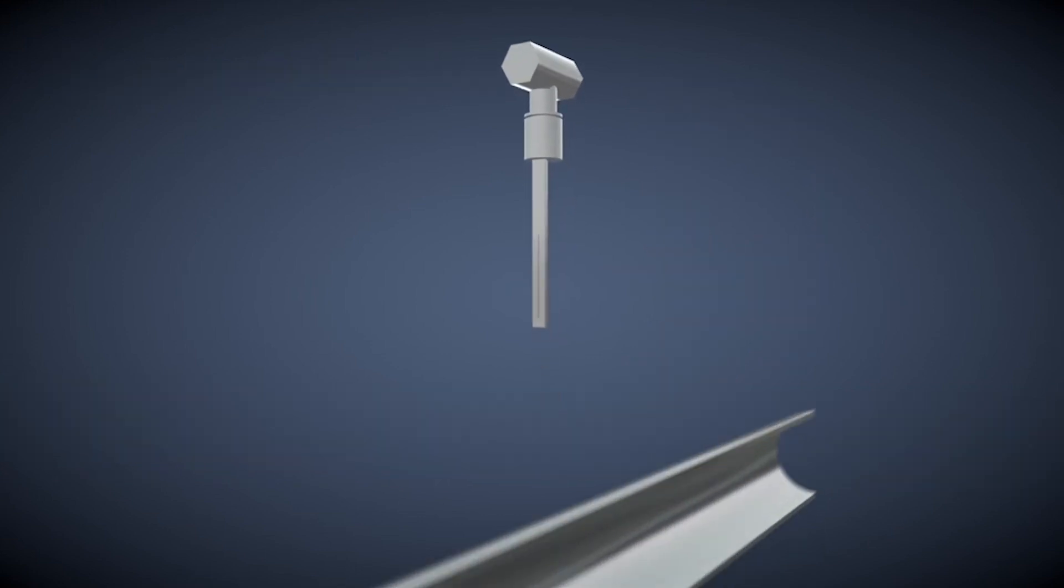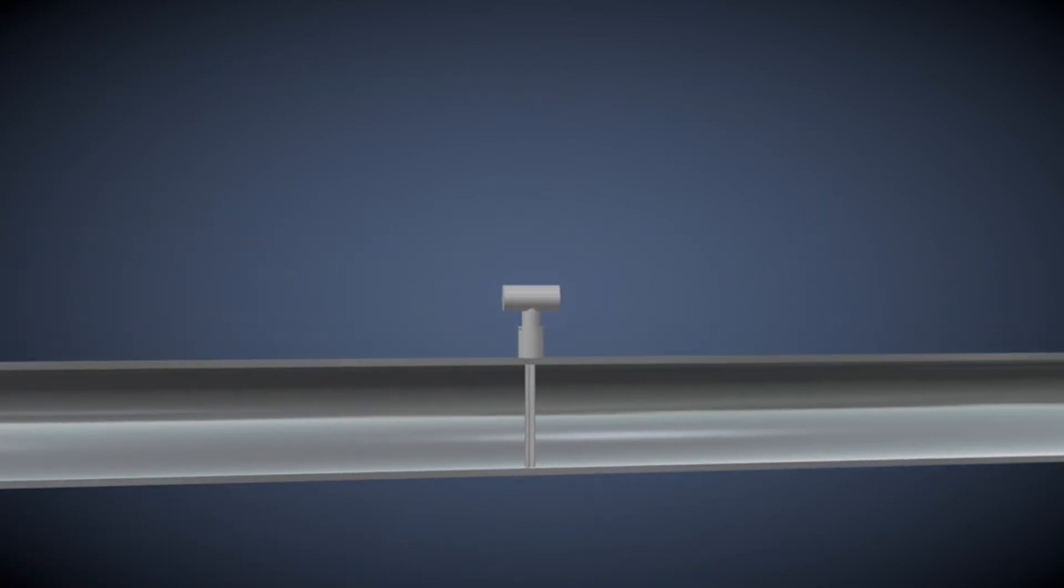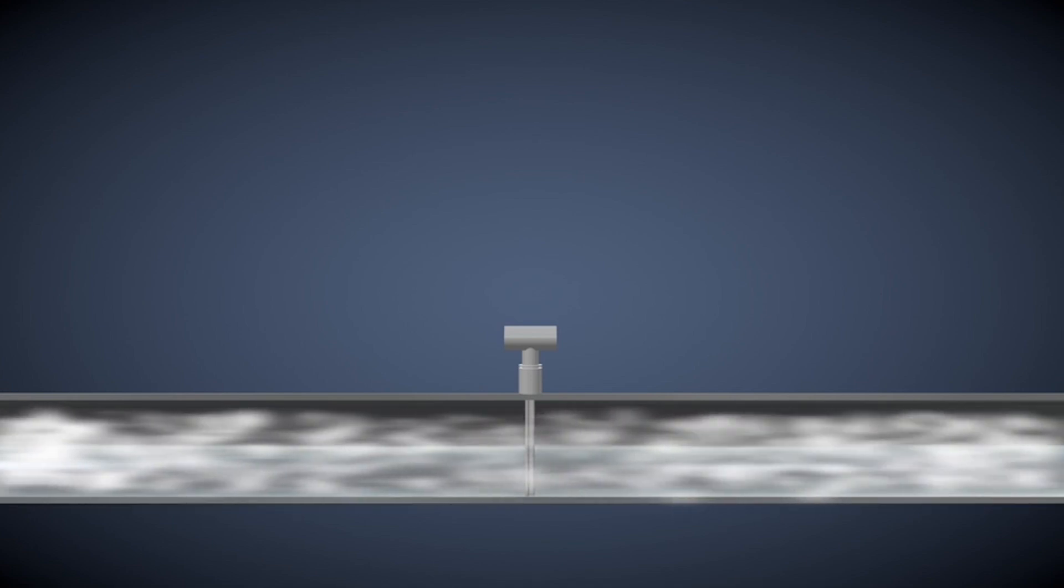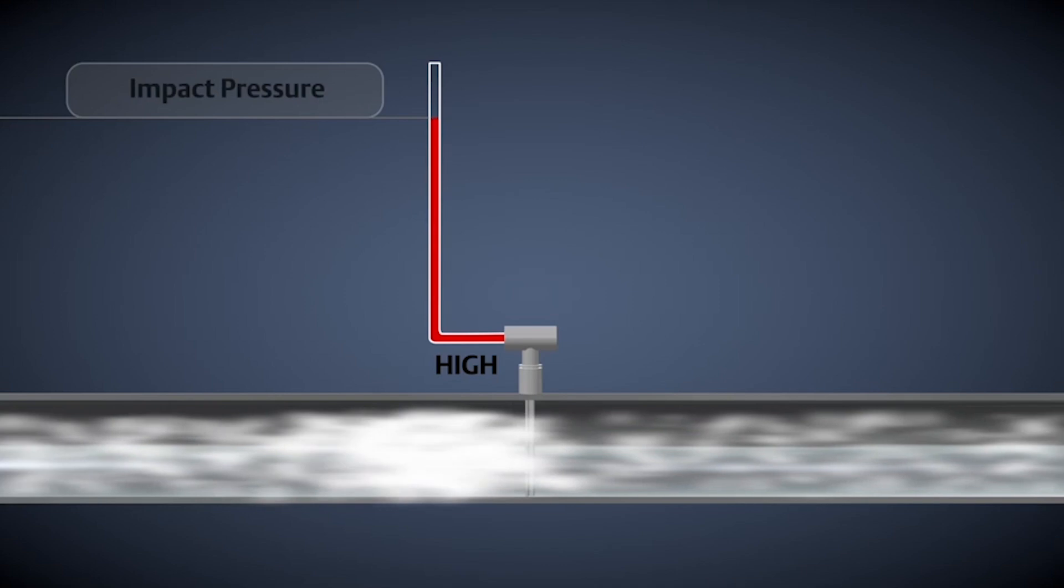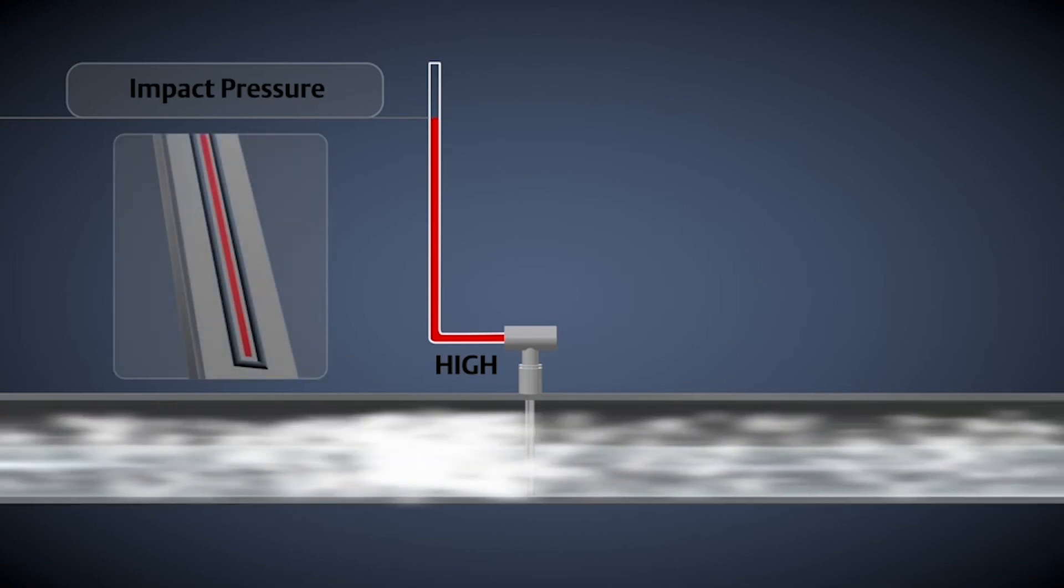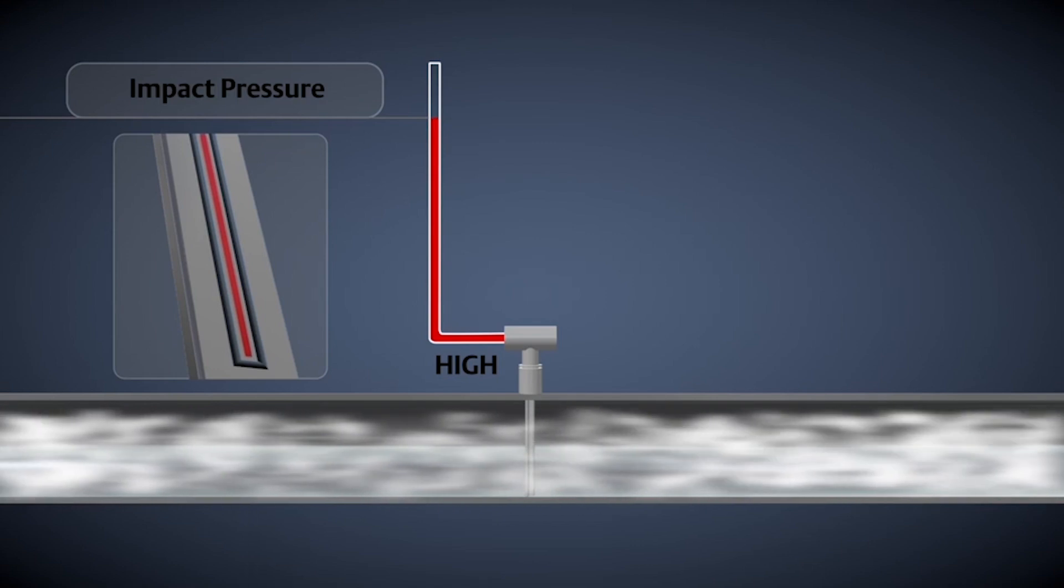The basic principle of operation for the Annubar flow meter is simple. As flow is moving down the pipe, it impacts the front side of the bar. This creates an impact pressure that is read by the slots in the Annubar sensor, capturing more of the flow profile for a more comprehensive and accurate measurement.